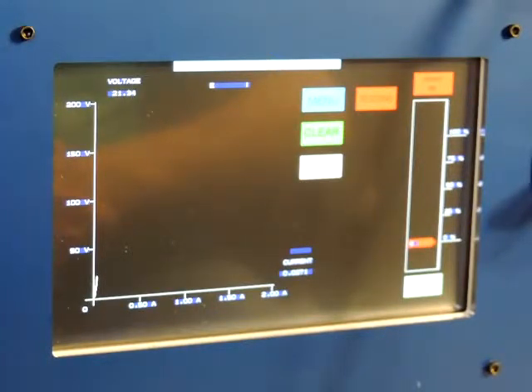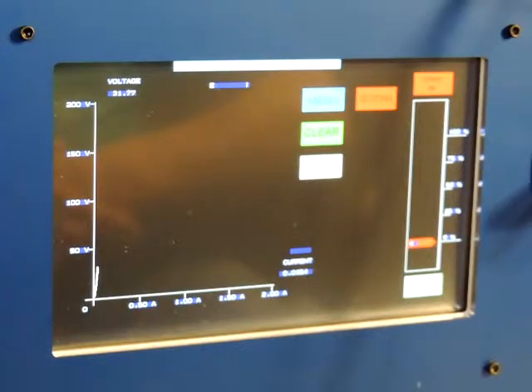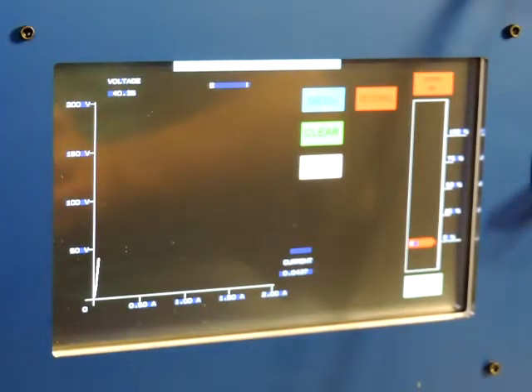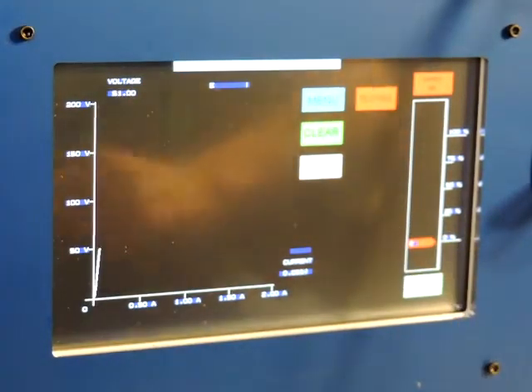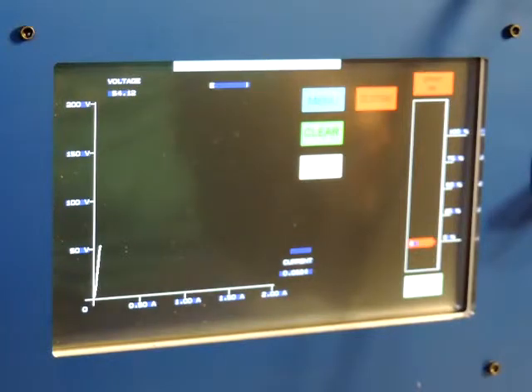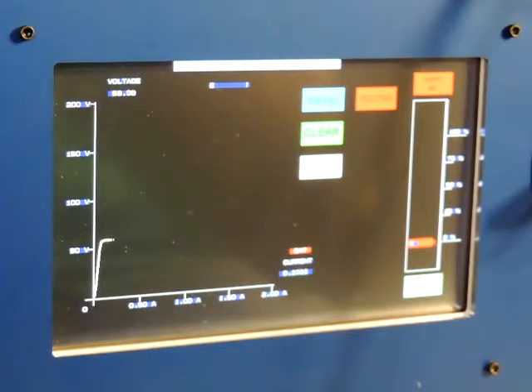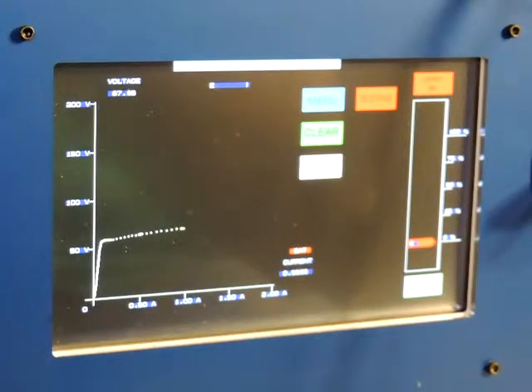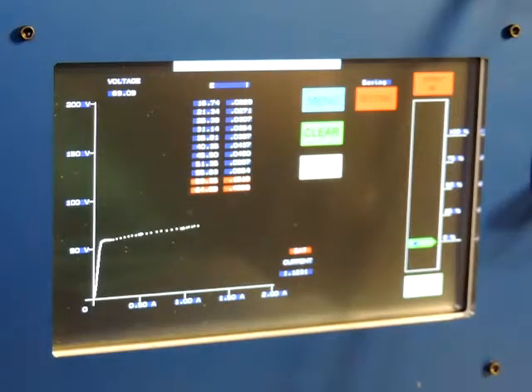You can see it's drawing a graph. The voltage output is increasing, and since it's below saturation it has a high inductive reactance — so the output voltage increases much faster than the current during this initial unsaturated phase. When it gets to the saturation point and measures a distorted exciting current, the SAT flag — a little orange flag — will say 'SAT.' This is coincidental with the break-over of the knee, where you can see the current climbs very rapidly for a smaller increase in voltage.